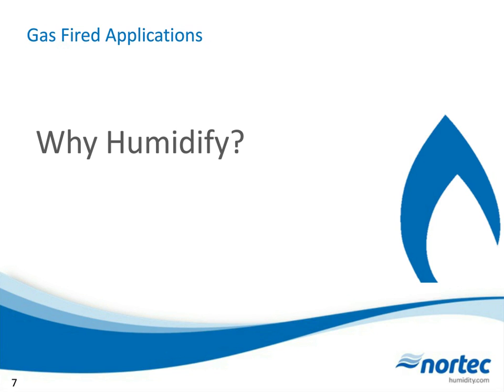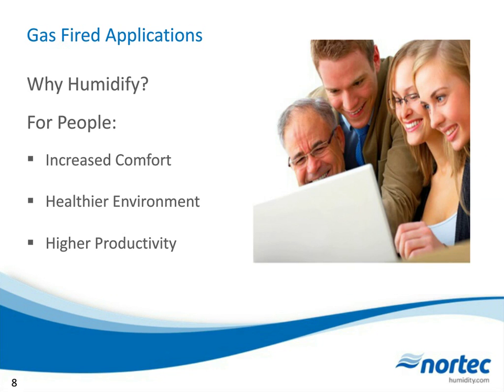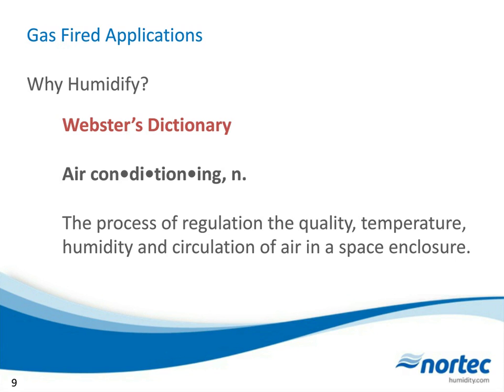Now let's touch on why humidify in general, before returning to gas-fired technology. The first reason is for people — for increased comfort, a healthier environment, and therefore higher productivity. Unfortunately, when we talk about air conditioning, the humidification part often gets dropped. It's about regulation of quality, temperature, and humidity in the space. I said healthier environment — why is humidity healthier? What does a 40% RH room do better than a 20% RH room? That's where I'd like to point out this chart — the Sterling chart, published by ASHRAE in 1985.